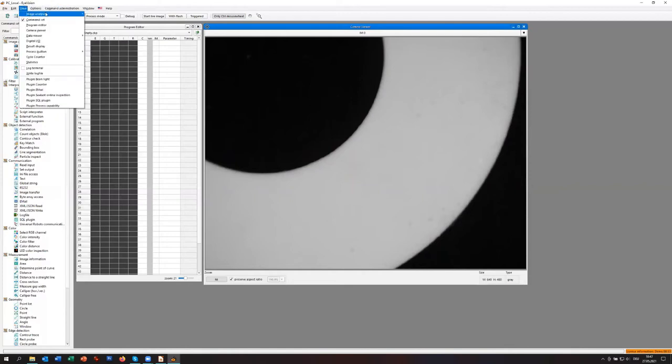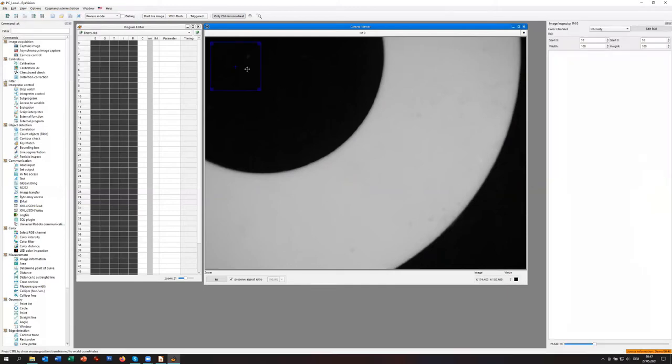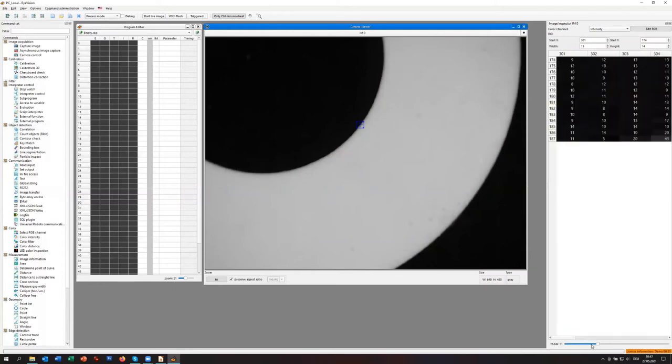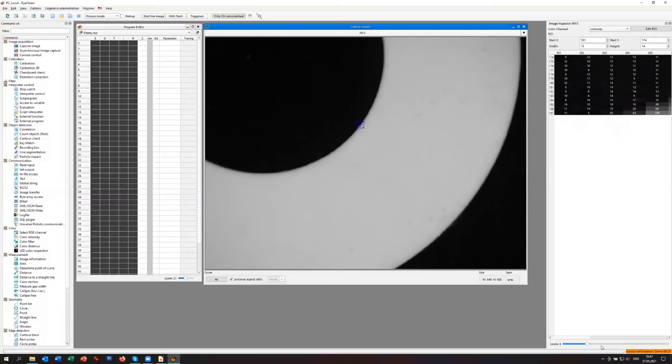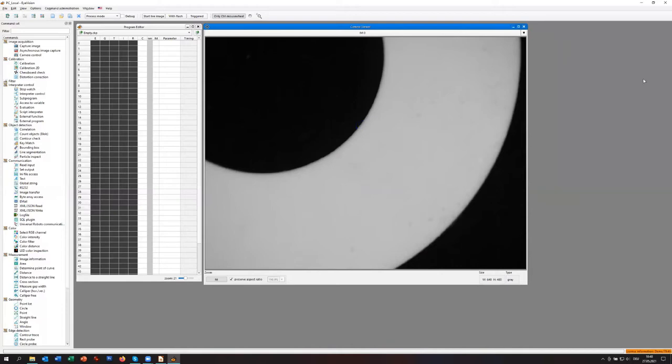So you have here some tools which allow you simply to look into the image and get an idea, for example, also the image inspector, of how good or bad an edge is. So if we have a close look at this edge and we change the zoom value, we can see how this edge looks. We start with 15, and at the edge we have a very fast modification to 166. This is a really good contrast. It's of course not zero to 255, but this is a contrast which allows stable measurements at the end. These options are mainly here to get a qualification of the image.